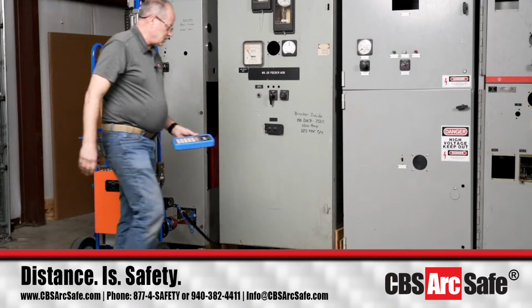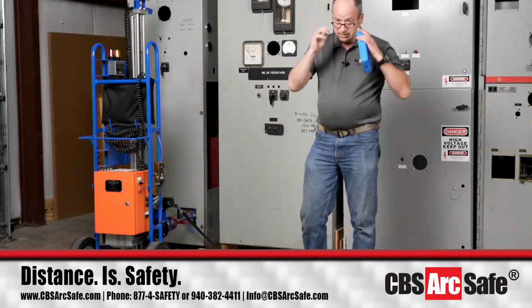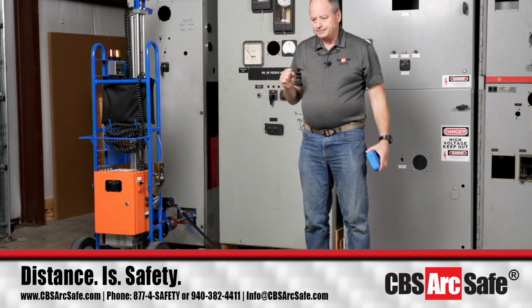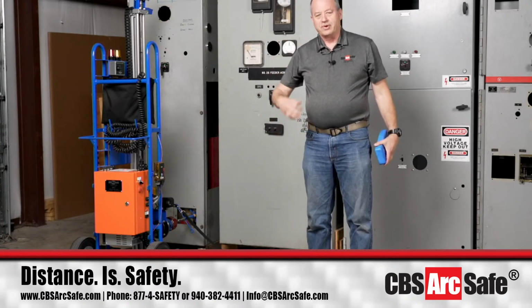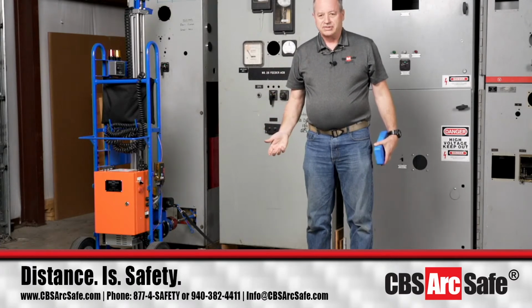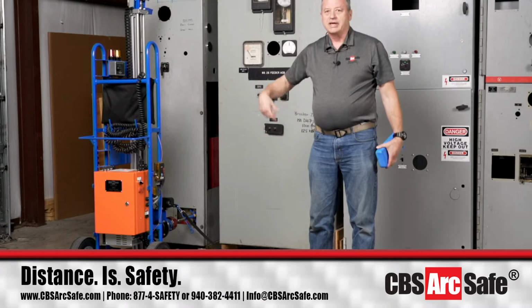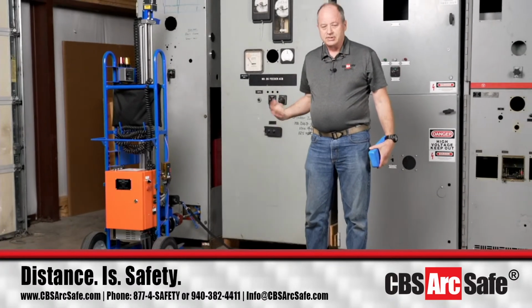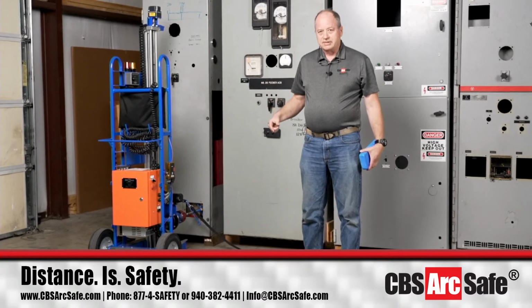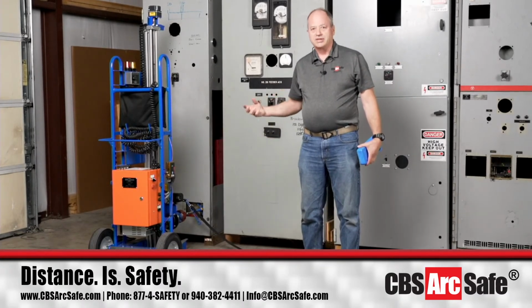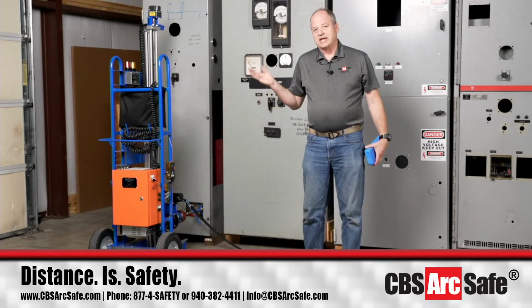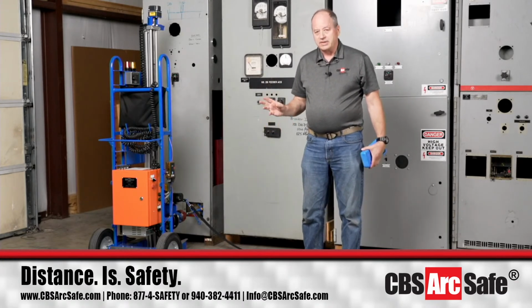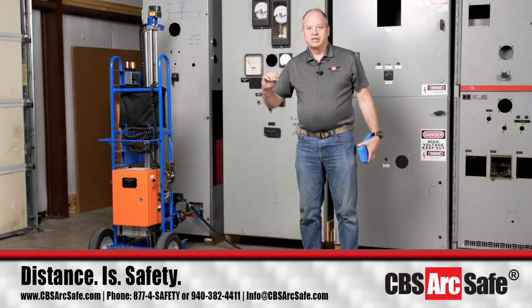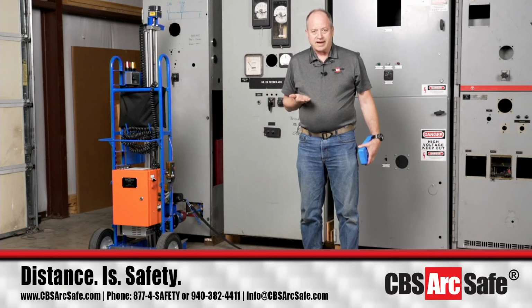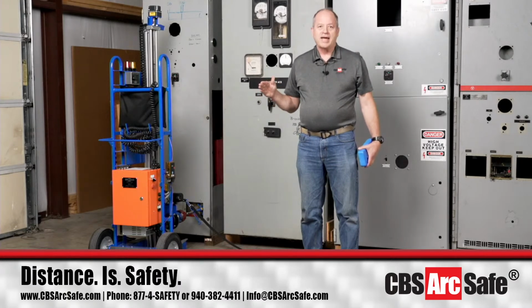So the funny thing is, when I first started doing this, it's sort of interesting. To rack the breaker fully out, what a person would have to do is release the latch, rack to the test position, release the latch, rack to the disconnect position, release the latch, rack it to the out position, you pull it out then, and that releases the springs. One of the things to note is you do not want to leave the latch pulled out during the racking process once you've got it moving.